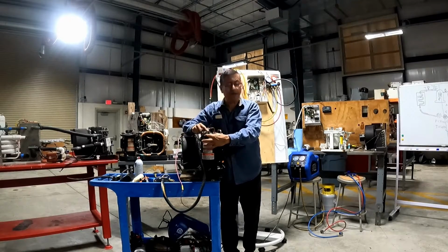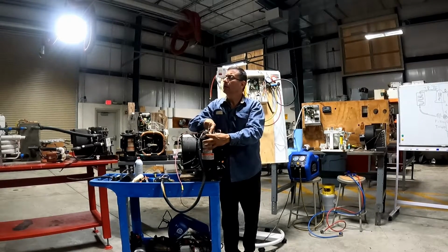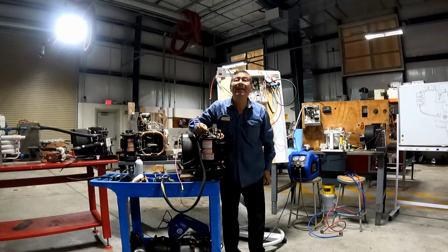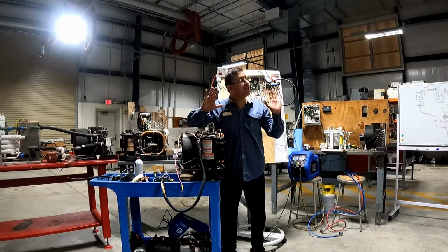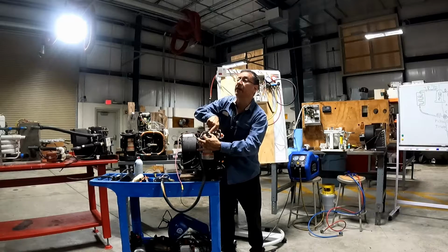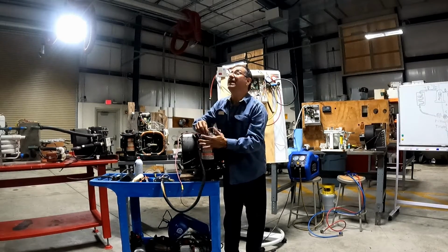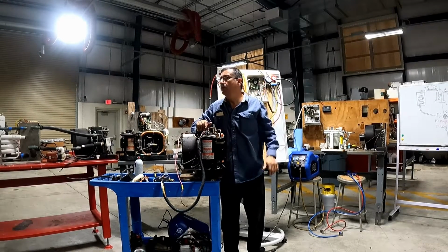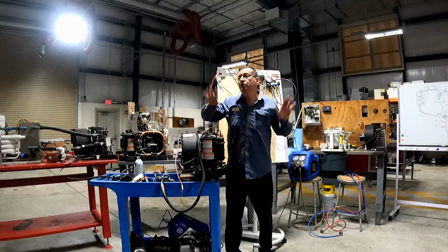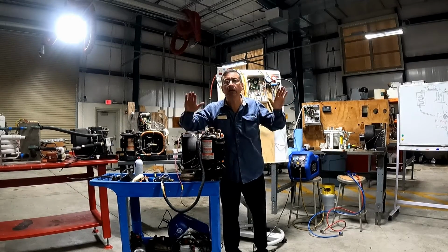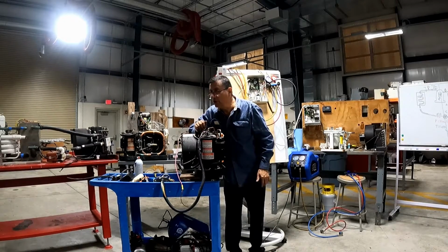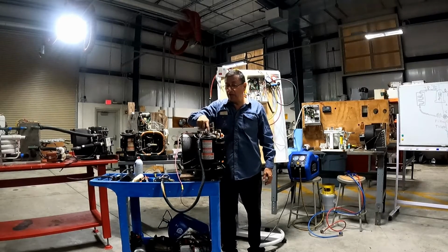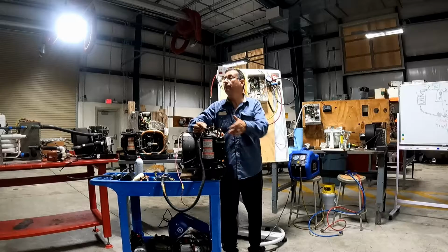Okay, I have power here, Mr. Lopez, but not here. In normal condition, this is a switch normally closed. If everything is okay and I have power here, I have power here, because it's normally closed. If the temperature is okay, it's accepted. If this is too hot, probably the switch stays open until the temperature of the body goes down. Mr. Lopez, the body is at ambient temperature, and I don't have power in the second terminal. What is the problem? It's broken, the thermal switch.